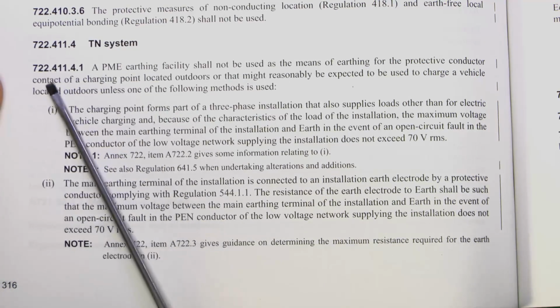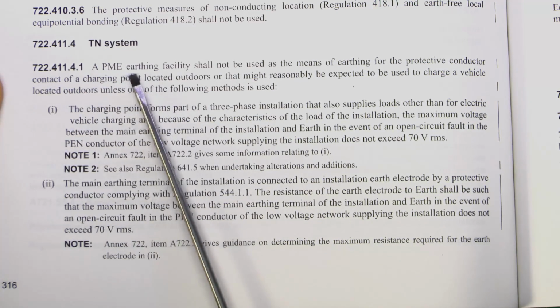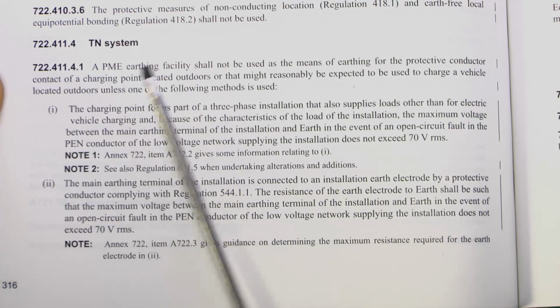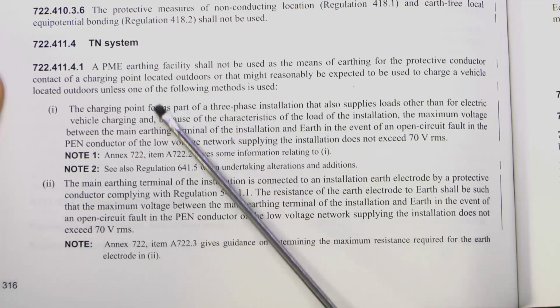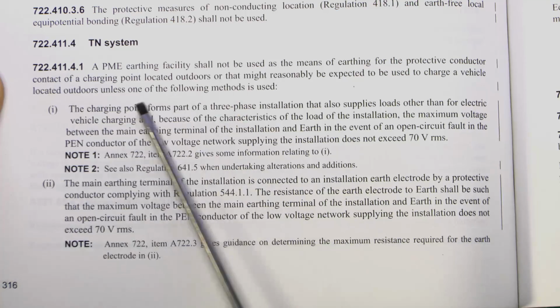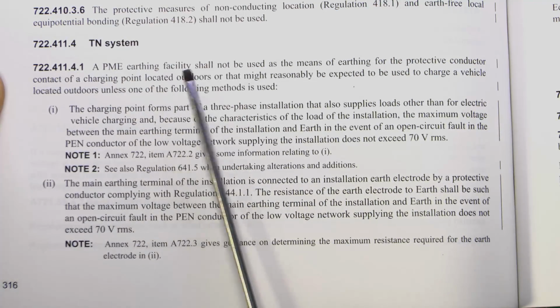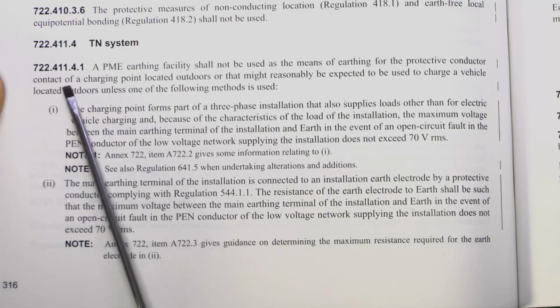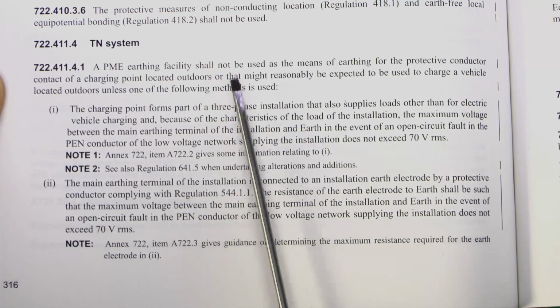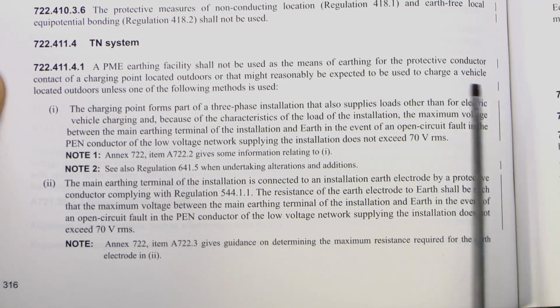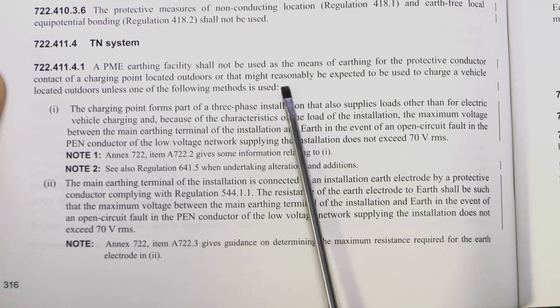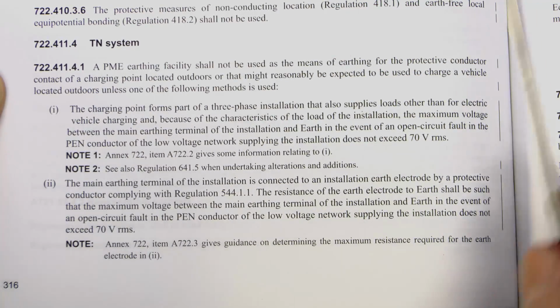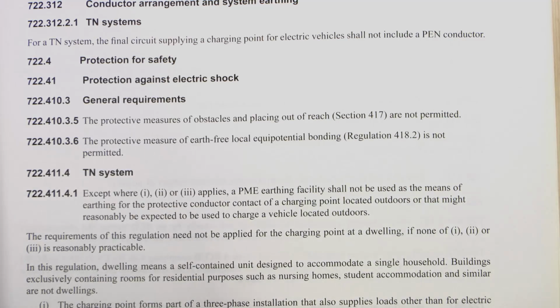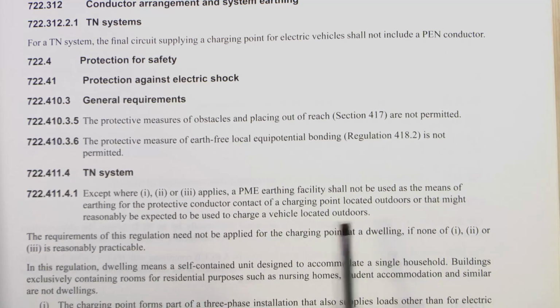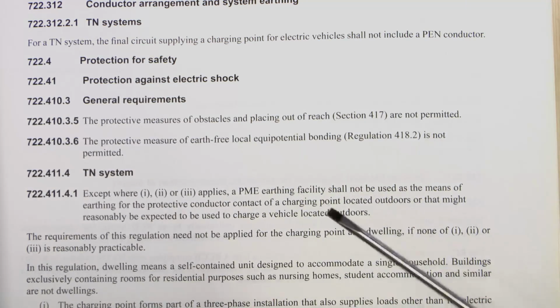Now 722.411.4.1 has been changed somewhat, and it's another one of these where a lot of the text is the same, although the actual arrangement of it has been revised. So what we've now got is a PME earthing facility shall not be used as the means of earthing for the protective conductor contact of a charging point located outdoors, or that might reasonably be expected to be used to charge a vehicle located outdoors, unless one of the following methods is used. And we've got the three methods 1, 2 and 3. Now this is what it said previously, and it was a similar thing except where 1, 2 and 3 applies, a PME facility shall not be used, and so on. So it's the similar thing, but it's been rearranged.